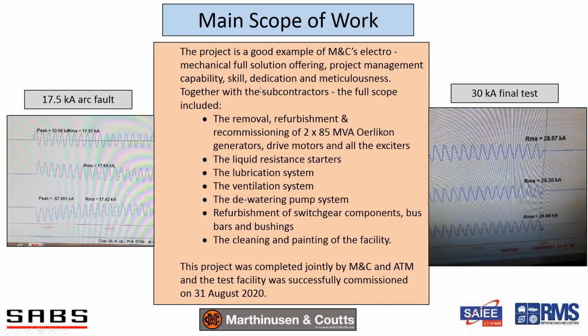Okay, now we can get on to the scope of work once you understand the plant. It's basically a full electromechanical solution, where the responsibility for both the electrical work and the mechanical work rested with one contractor, which is very attractive to, in this case, SABS or any customer. There were a couple of subcontractors, most notably, as I mentioned before, our sister company Actom Turbo Machines. So the scope was the removal, refurbishment and recommissioning of the two 85 MVA Oerlikon generators, their drive motors and all the exciters. There were commutators on the DC machines that had problems. The drive motors, amazingly, were still in very good condition.